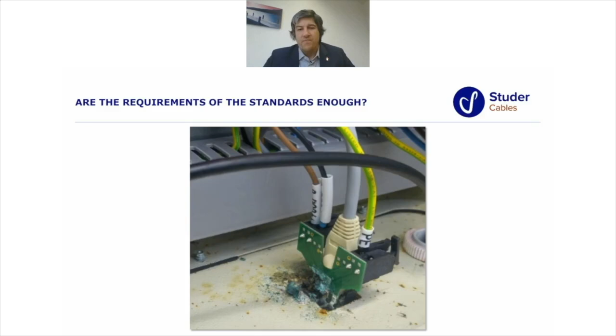Now, let's leave the floating PV and go to other examples. If we talk about quality, 50% of the quality is determined by the planning phase. You need to decide on the right components to be used. The list of materials should be appropriate to the installation. And certainly you also need to calculate correctly all the electrical parameters which are going to be used in your installation. In this particular 3 megawatt rooftop installation, we see a trouble of insufficient arcing protection combined with underestimated resistance capacity of the cables. In other words, the wrong cross-section of the cables has been used. The result is that the PV plant is out of operation for a long time. And by the way, replacing the cables is a very complicated and very expensive discipline at the end of the day.